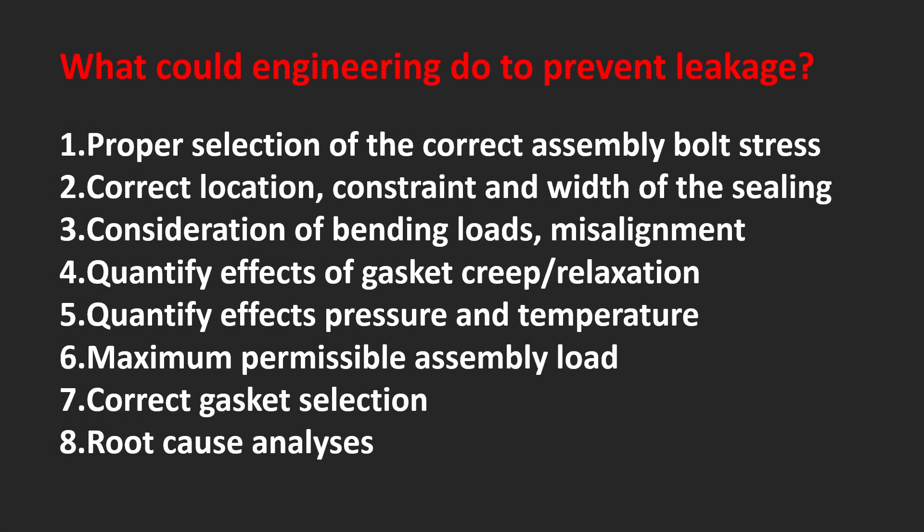What could engineering do to prevent leakage? Proper selection of the correct assembly bolt stress, correct location, constraint and width of the sealing, consideration of bending load misalignment, quantify effects of gasket creep relaxation, quantify effects of pressure and temperature, maximum permissible assembly load, correct gasket selection, and root cause analysis.